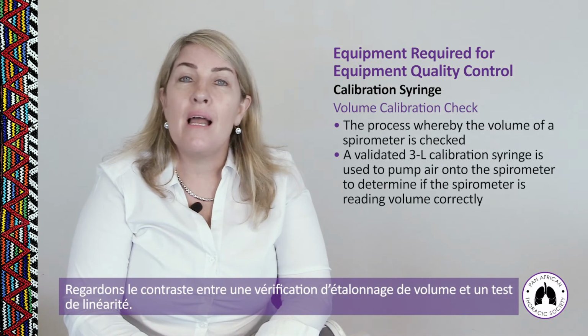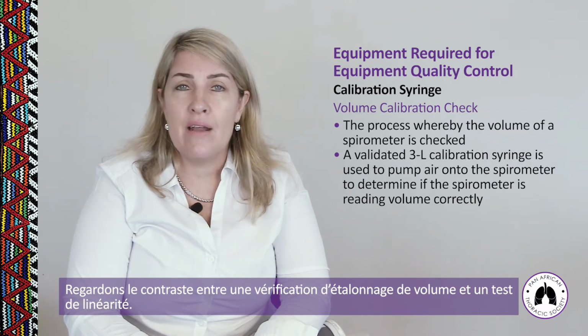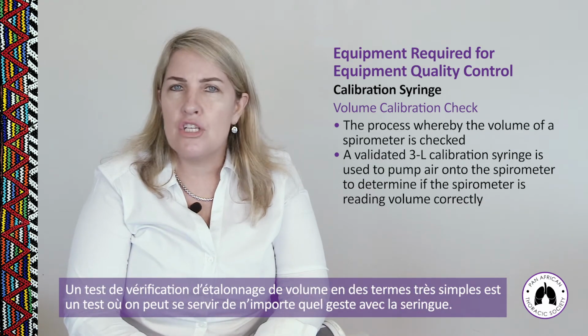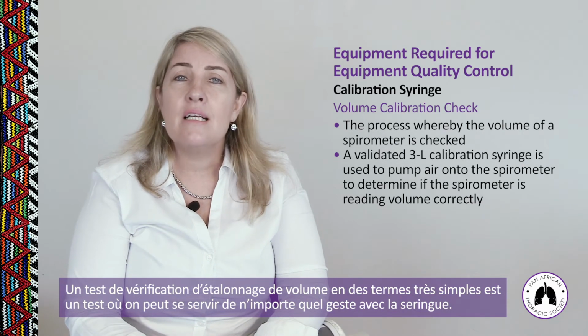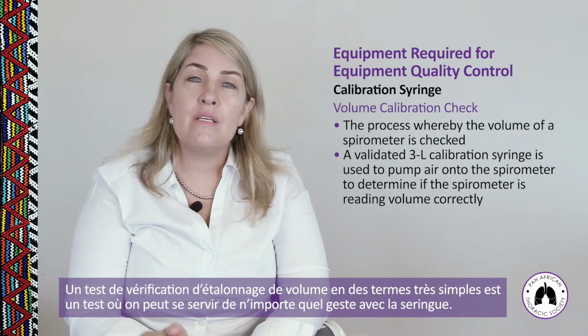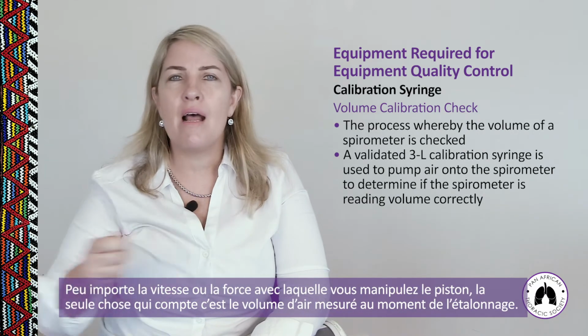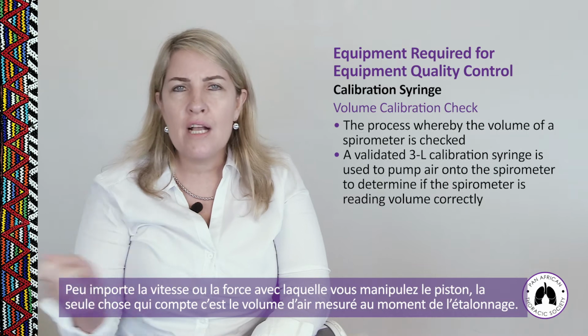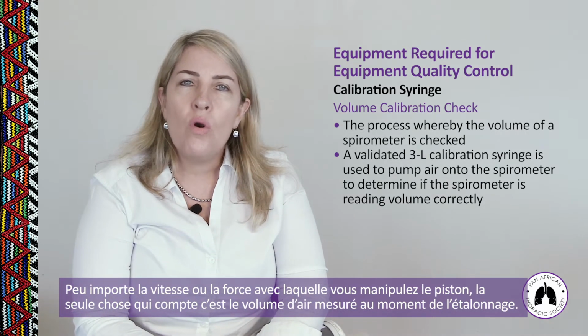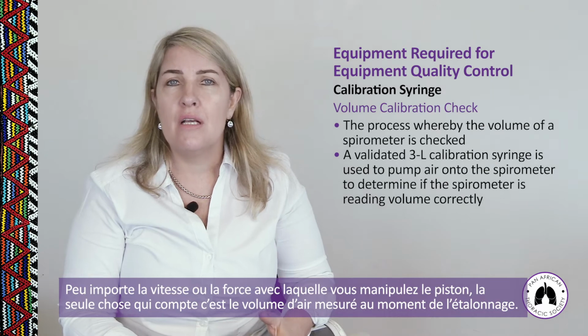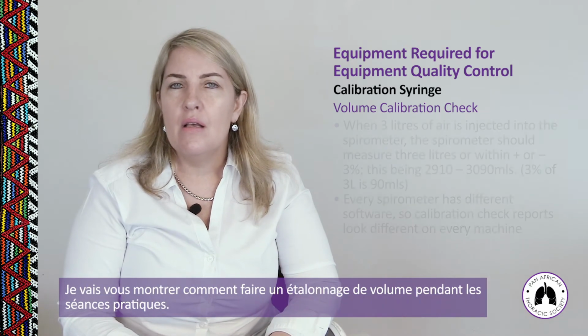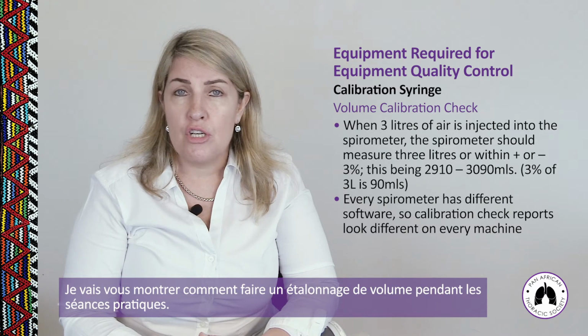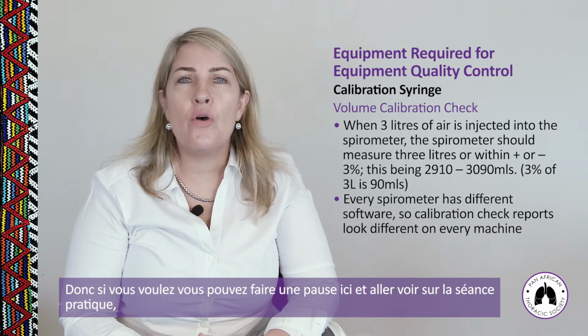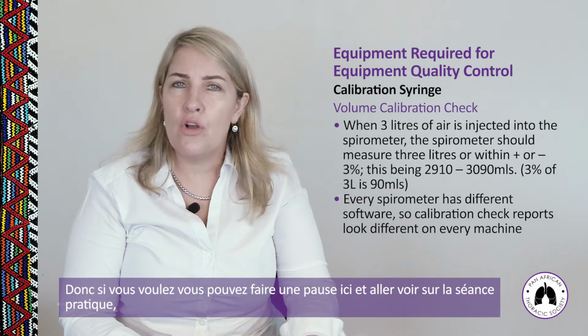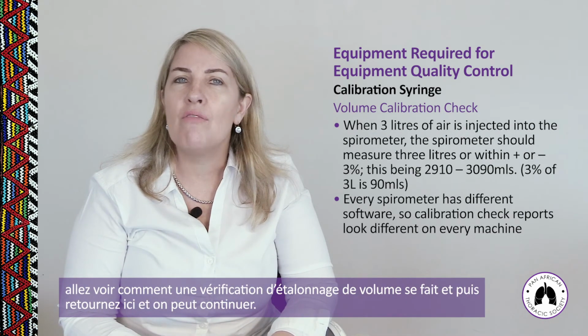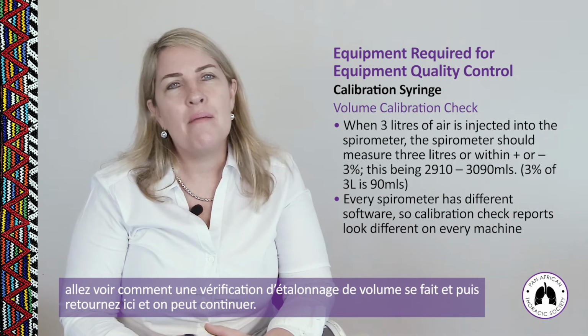Let's look at what a volume calibration check is then versus a linearity test. So a volume calibration check very simply is conducting a calibration check on a device using any syringe stroke. So it doesn't matter how fast or how slowly you actually move the syringe plunger, it's all about the volume of air measured at the time of calibration. I'm going to show you how to do a volume calibration check in the practical sessions. So if you would like to halt at this point and go to the practical session, go and have a look at how a volume calibration check is done, and then come back and let's carry on.